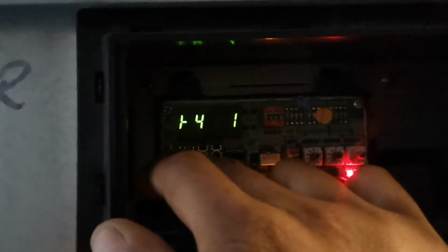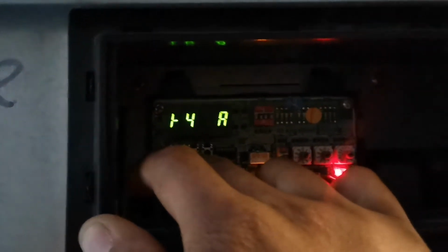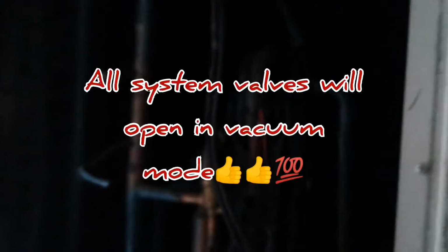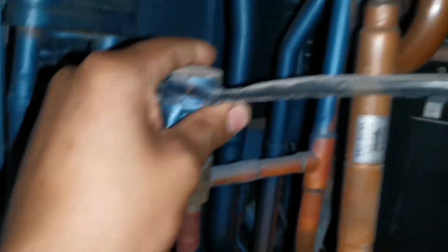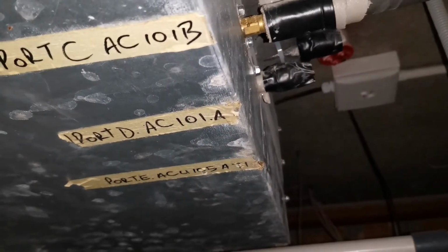Let's open up all these valves. There we go. And you will hear that it will start opening valves on the outdoor. Expansion valves are opening, because there's quite a few of them on these condensers for different functions, like the vapor injection for the compressors and the cool line that cools down the IPMs, the inverter power modules. Alright, so I think we can go and have a look. Hopefully we can detect this leak right now. Alright, so this is our MCU unit, master control unit, as you can see.